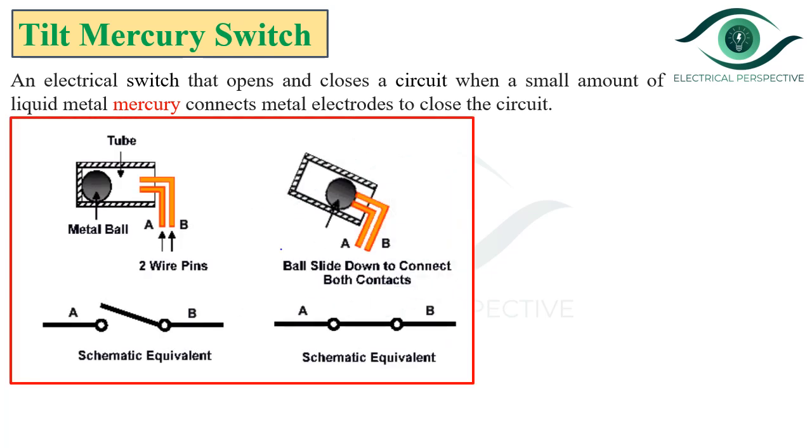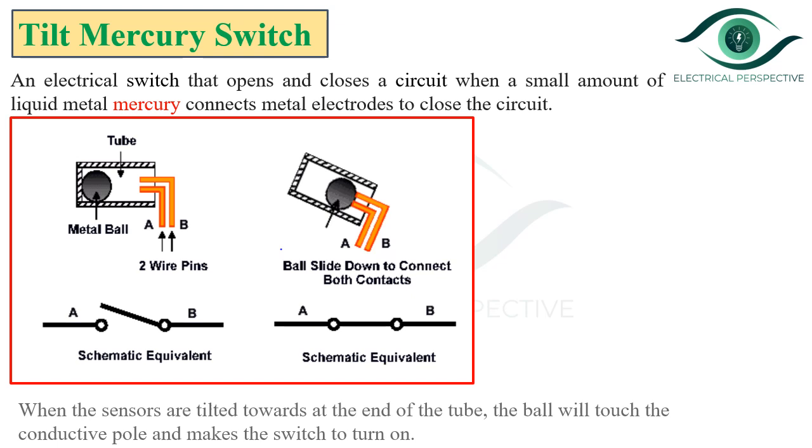Before discussing the actual working principle of Buchholz relay, let us see the working of the tilt mercury switch. It is an electrical switch that opens and closes a circuit when a small amount of liquid metal, i.e. mercury, connects the metal electrodes to close the circuit. In figure 1, the tube is in the horizontal position, meaning there is no electrical connection between the metal ball and electrodes, and therefore the circuit is open. When the tube gets tilted, the ball will touch the conductive poles and makes the switch turn on. This is the working of the tilt mercury switch.